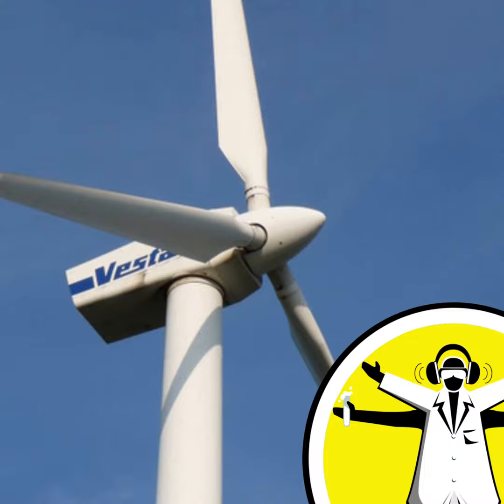We designed turbines specifically to harness the Antarctic wind, which is quite extreme compared to other wind sites in the world. And how did you set about designing this turbine for this particular environment? First of all, the most important obstacle is the low temperatures in which the turbine should function. In that case, we spent some time selecting specific materials that can cope with low temperatures, varying from plus 10 degrees Celsius to minus 40 degrees Celsius in the winter. So the steel, we select steel that has a high carbon content. We select the epoxy for the blades that is also used in aircraft design. And we kept the turbine itself as simple and robust as possible, meaning less parts, more reliability.